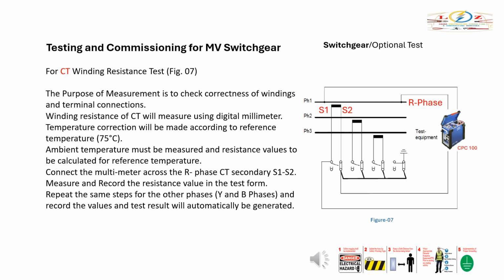For CT winding resistance test, as shown in the arrangement drawing in Figure 7, the purpose of measurement is to check correctness of windings and terminal connections. Winding resistance of CT will be measured using a digital multimeter. Temperature correction will be made according to the reference temperature of 75 degrees Celsius. Ambient temperature must be measured and resistance values calculated for the reference temperature.